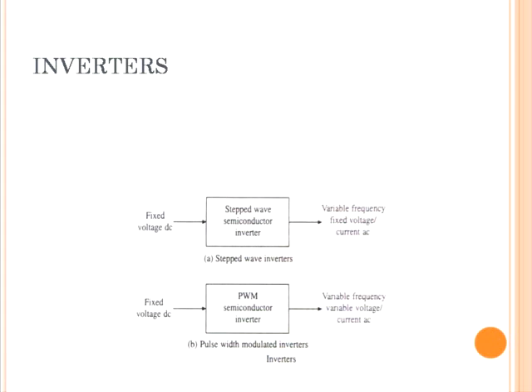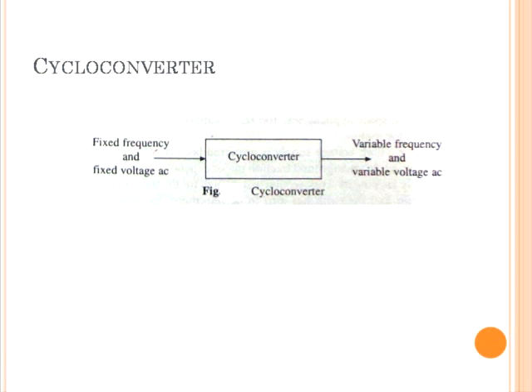Cycloconverters convert fixed voltage and frequency AC to variable voltage and variable frequency AC. They are built using thyristors and are controlled by firing signals from a low power control unit. Output frequency is restricted to 40% of the supply frequency in order to keep harmonics in the output voltage and source current within acceptable limits.